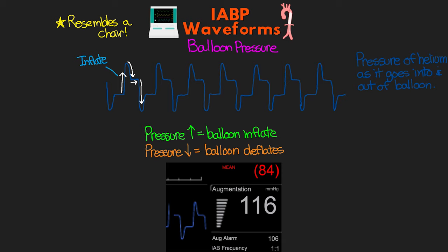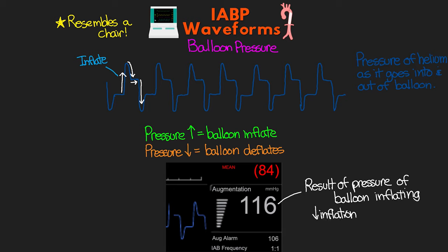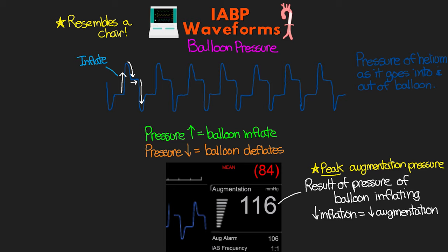The augmentation shown to the right on the display is a result of the pressure caused by our balloon inflating. If we decrease the amount of inflation — also known as augmentation — you would see the augmentation pressure shown in white decrease as well. This value only shows the peak augmentation pressure and really only changes over time as the highest peak pressure changes. This could be the result of us changing the augmentation on the console or from patient-specific physiologic factors. Generally, this number remains relatively stable when there are no changes.